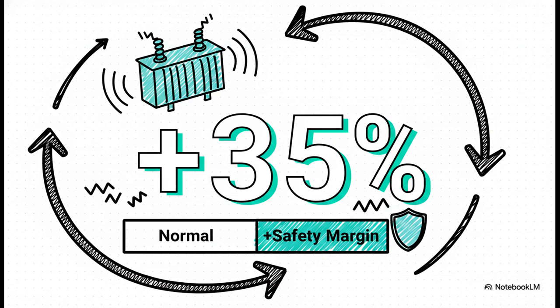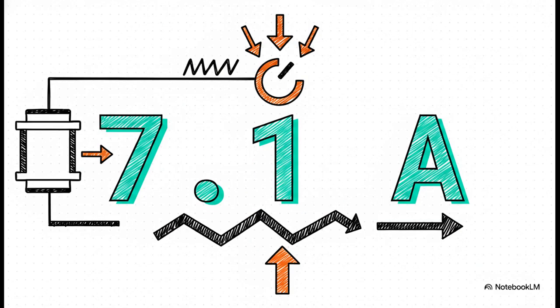Now, you can't just set the tripwire right at 5.25 amps, right? Because power demand goes up and down, and you get tiny, harmless surges all the time. To stop the system from shutting everything down for no reason, what engineers call nuisance tripping, you have to build in a little bit of a safety margin. A buffer of about 35% above normal is a pretty common choice. And that gets us to our magic number.